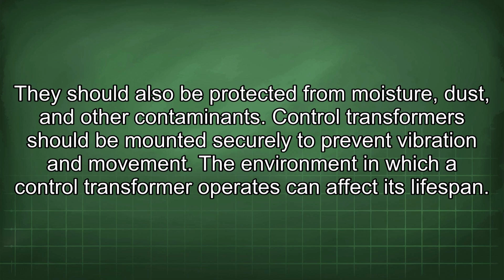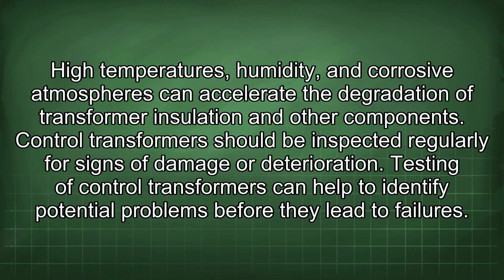The environment in which a control transformer operates can affect its lifespan. High temperatures, humidity, and corrosive atmospheres can accelerate the degradation of transformer insulation and other components. Control transformers should be inspected regularly for signs of damage or deterioration.